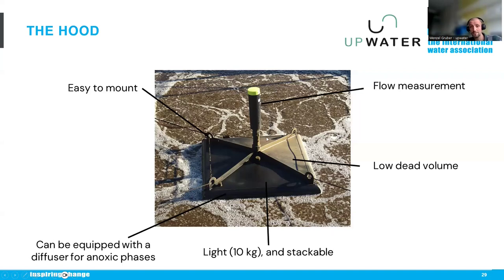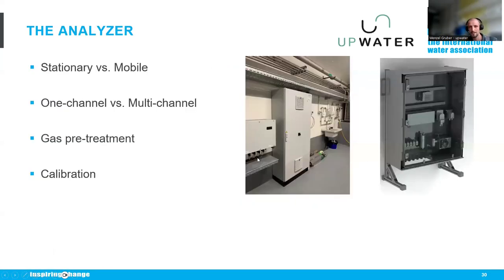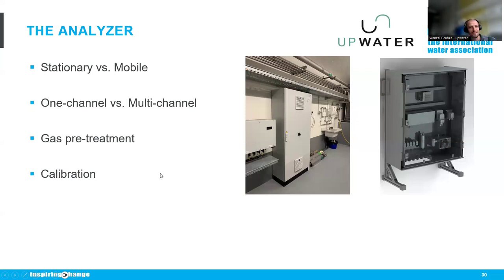NOTOS has a local airflow measurement developed by ETH Zurich on top of the hood. The analyzer connected to the hoods can be stationary or mobile, with one channel or multi-channel depending on needs. There is a gas pretreatment that robustly removes all liquids and activated sludge from the off-gas, and calibration is done automatically — very different from liquid sensors and a very low-maintenance approach.